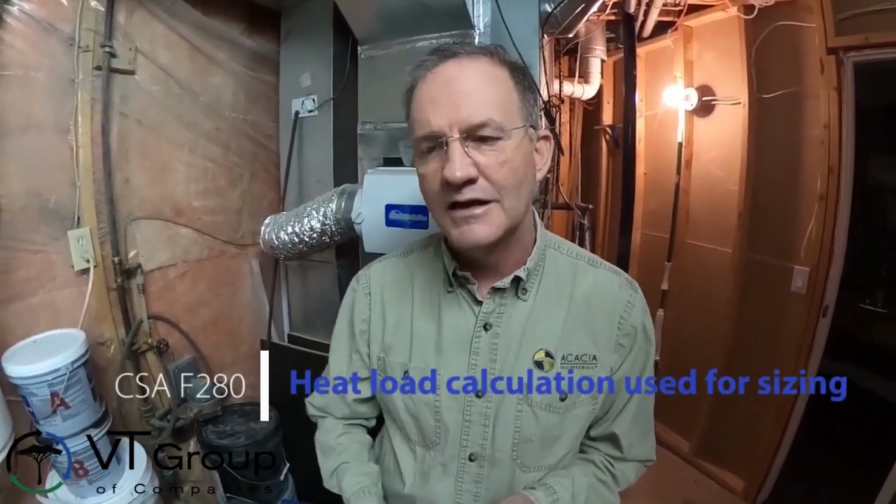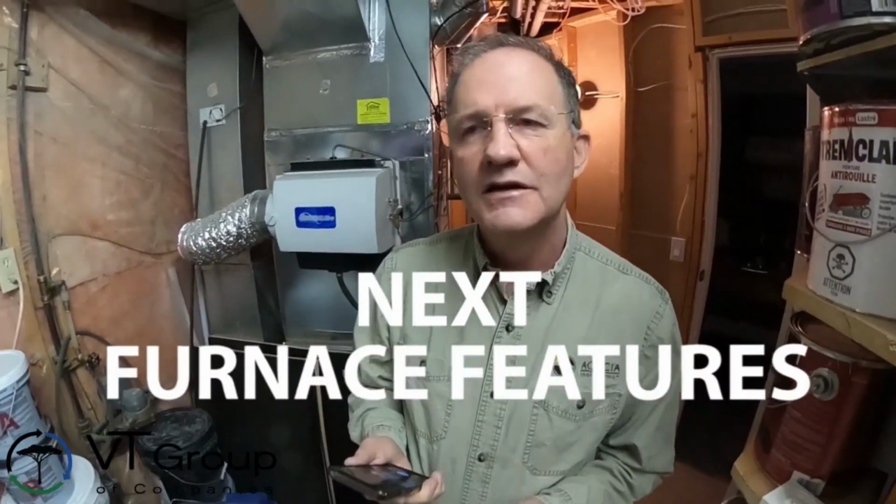So a heat loss calculation, which is what we call CSA F280, yes, you can contact us at energyexperts.ca and we can help you with that. If you do an ERS, EnerGuide Rating System, through the Greener Homes program, there is a heat loss in there. That is still the responsibility of the heating contractor to size it, but it will give you a guide on sizing of a furnace. So now that you've got your size, you know how big it is, and that's BTU per hour, you want to think about some of the other features, right?